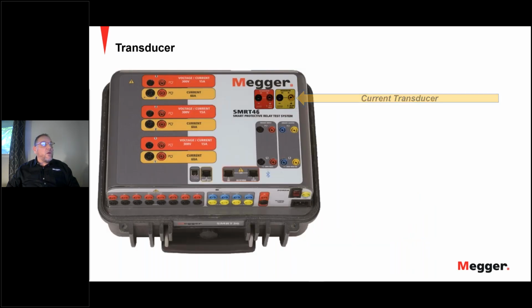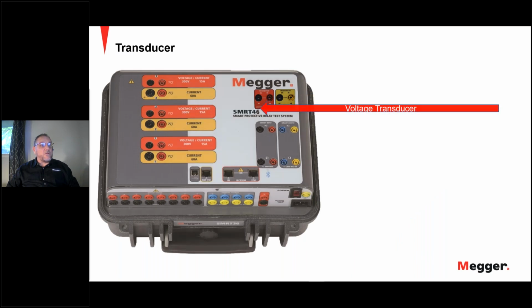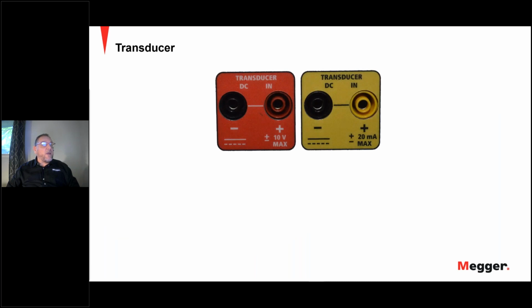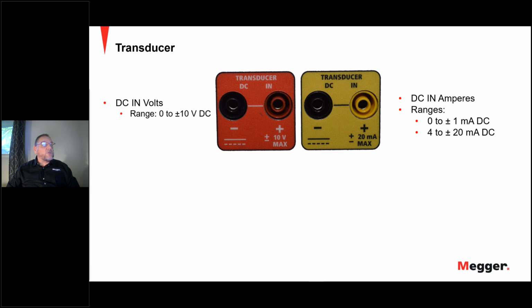Then moving on, the unit has an optional transducer input that can be provided, and these inputs can be used to test different types of voltage and current transducers using the appropriate forms in PowerDB. So you've got a DC in volts with a range of 0 to plus or minus 10 volt DC, and a DC in amps, which ranges from 0 to plus or minus 1 milliamp DC, or 4 to 20 milliamp DC.